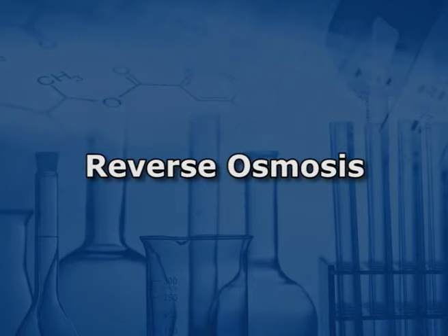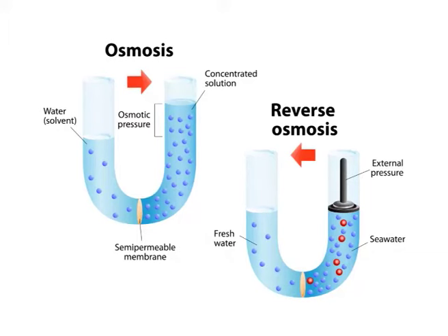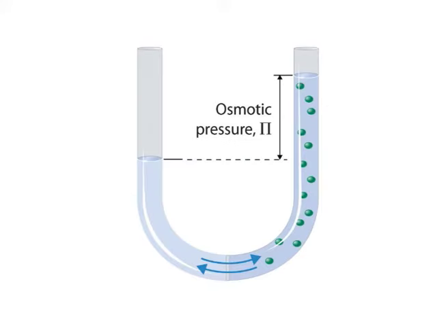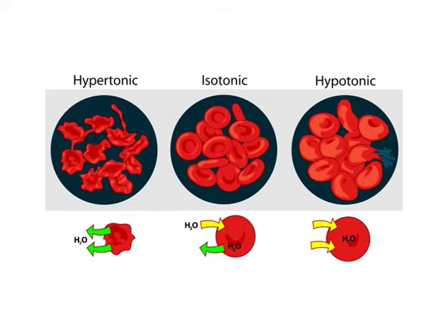Another method is reverse osmosis. As the name suggests, the natural process of selective permeation of molecules through a semi-permeable membrane separating two aqueous solutions of different concentration is reversed. Pressure of 200 to 400 psig is applied to overcome osmotic pressure and force pure water to permeate through the membrane. The membrane usually consists of cellulose esters or polyamides.